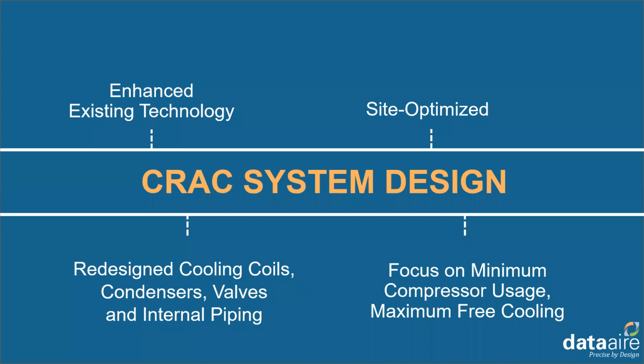So let's take a closer look at the Data Aire site-specific solution and how we met all of the owner's goals. At the time Swanson Ring brought us into the project, Data Aire didn't have a system that met their criteria either, but we were willing to work with the engineer to develop one, and all of our competitors passed on that opportunity. So here's what we did. To minimize the risk associated with designing a completely new unit, we started with our dual cooling unit, which is a tried and true technology, and then we optimized that unit for the 21st century data center conditions.